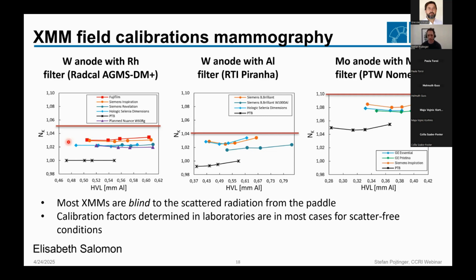But most of the XMMs won't see that scattered radiation. For example, the RTI Piranha, on top of the diodes, has a very tight collimation that will just remove all of the scattered radiation. So of course, your ionization chamber will see that. Your XMMs will not see that.